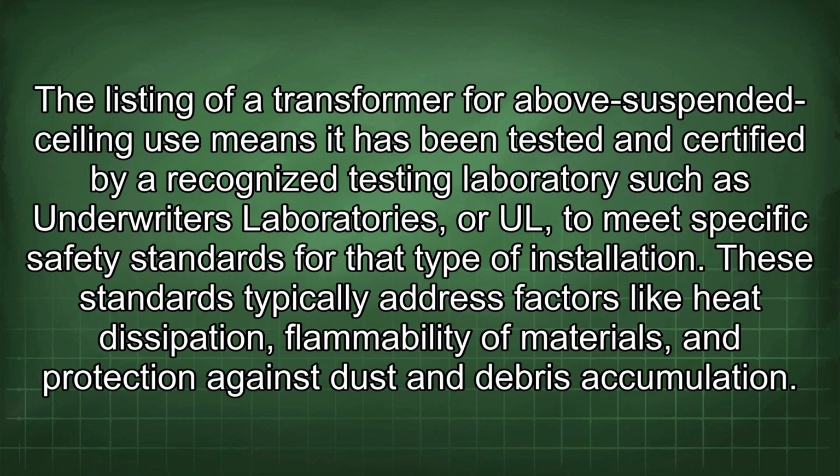The listing of a transformer for above suspended ceiling use means it has been tested and certified by a recognized testing laboratory, such as Underwriters Laboratories, or UL, to meet specific safety standards for that type of installation. These standards typically address factors like heat dissipation, flammability of materials, and protection against dust and debris accumulation.